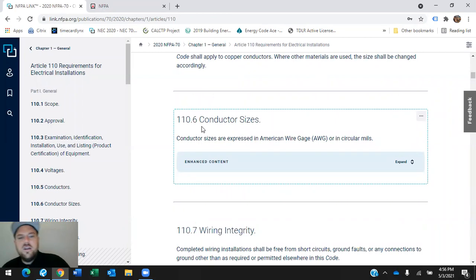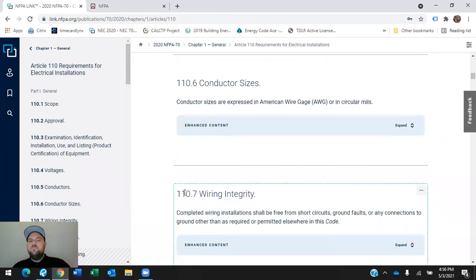Conductor sizes are expressed in American Wire Gauge, AWG—I like to say AUG, but you can say it however you like—or in circular mils. You've got your 12 gauge, 10 gauge, 8 gauge, all the way down, and then going up to 22 gauge. We've got our 0 to 10 wires that are typically somewhere between a 16 and a 22 gauge, for our 0 to 10 volt dimming and things like that.